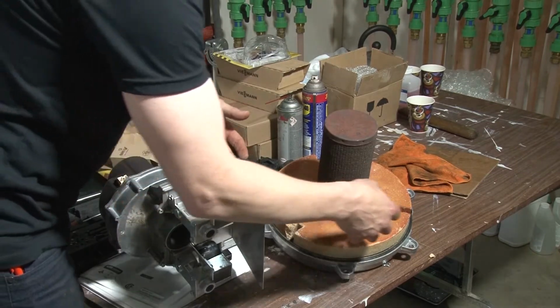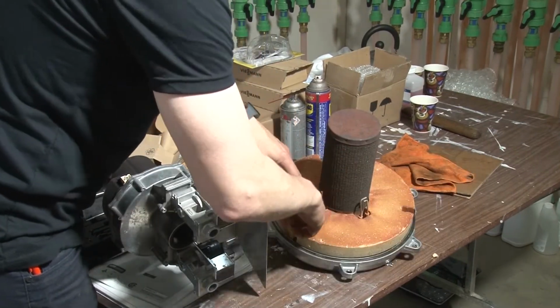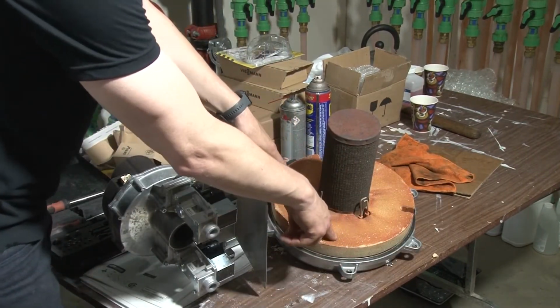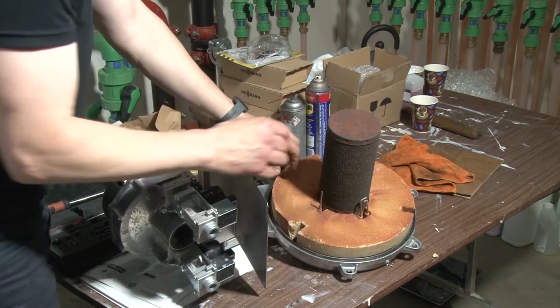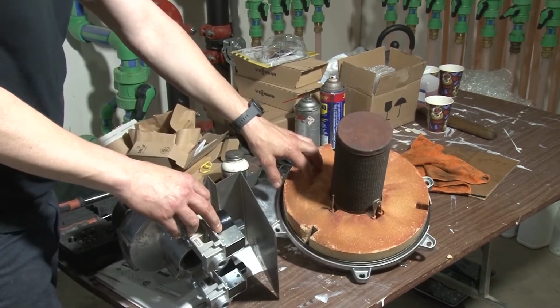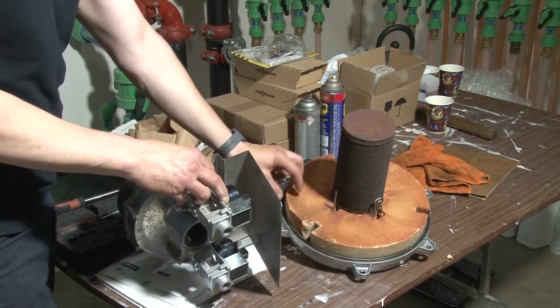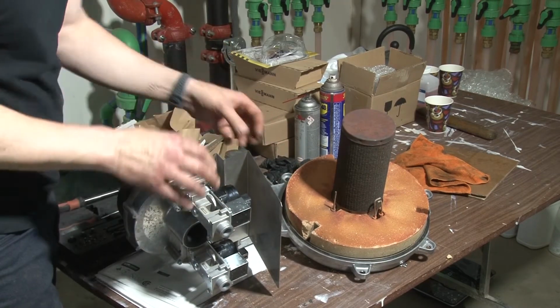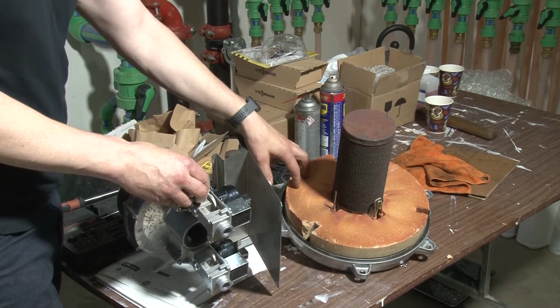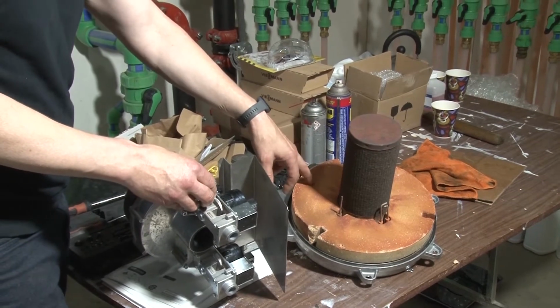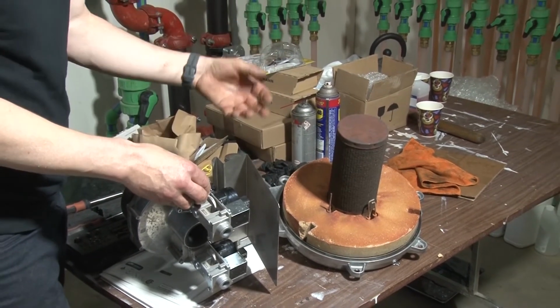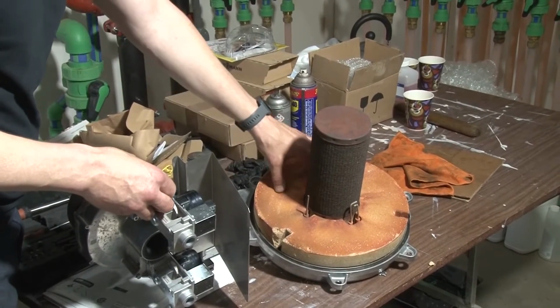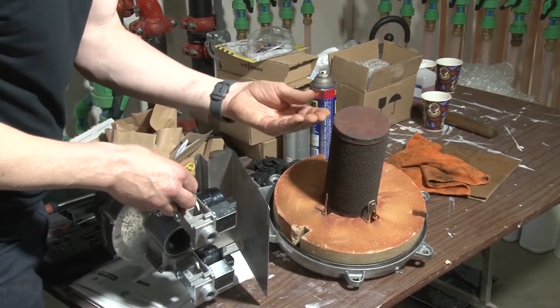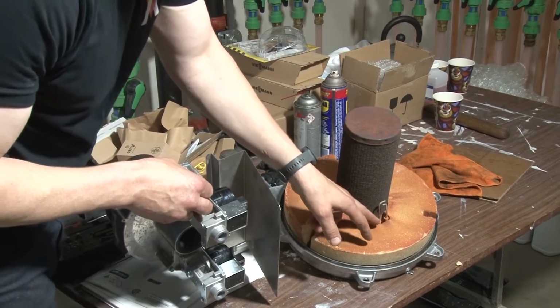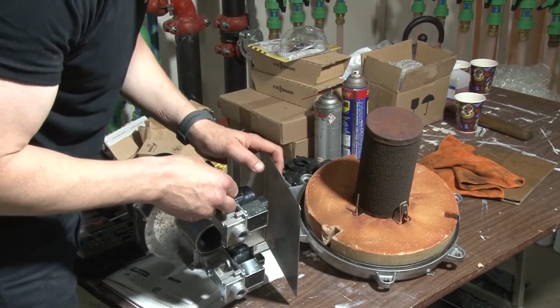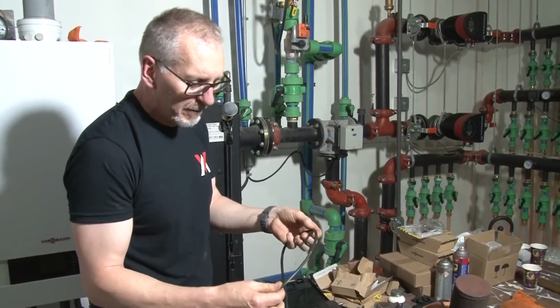It's not loose. And also that I don't see any tide marks in here where water's been inside the heat exchanger. As soon as this thing gets hit with water, it's like a sponge, and it loosens up the refractory that's been pressed. And of course it's going to start to flake. So if I see water marks on them, I'll replace them as just a preventative measure. But if they're dry like this, again it just has that kind of sign of combustion air contamination. You can see it here a little bit on the electrodes and stuff like that as we inspect them. And I'm just going to put it back in.